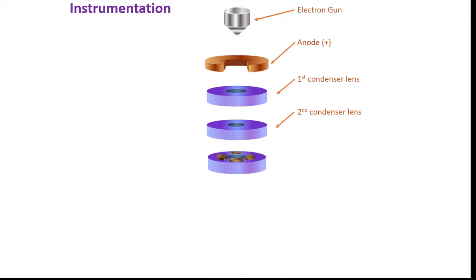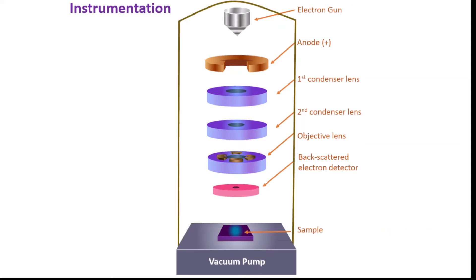Now let's see the instrumental setup of the scanning electron microscope. It starts with the electron gun, which is the main source of electrons. Then there is the anode, which is positively charged, and its function is to guide the produced electrons from the electron gun. Then the first and second condenser lenses give a proper shape to the electron beam. It then passes through the scanning coil or objective lens. There is also a backscattered electron detector, and the sample sits on the sample stage. The total system must be in proper vacuum.